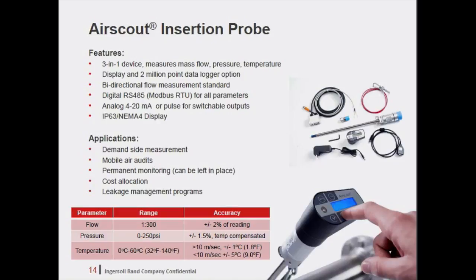Getting into the details with each of the products, the Airscout Insertion Probe is a 400 mm probe with the capabilities to measure mass flow, pressure, temperature, along with that bidirectional flow measurement as a standard feature. There's also a 600 mm probe that's available for larger pipe installations. To communicate out these readings, the flow meter can connect to either a digital display with 2 million data point logger or a connector cap.